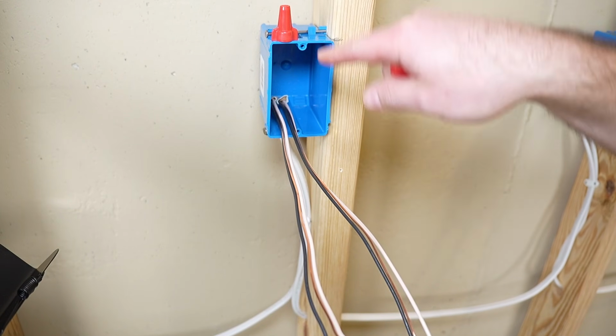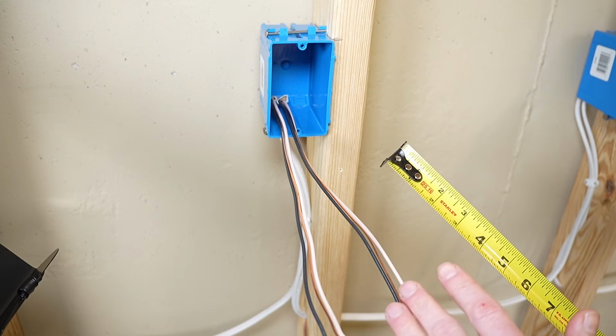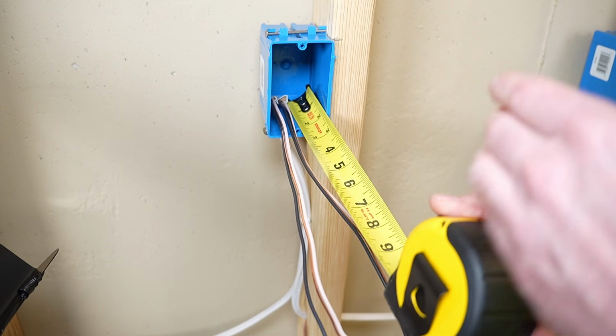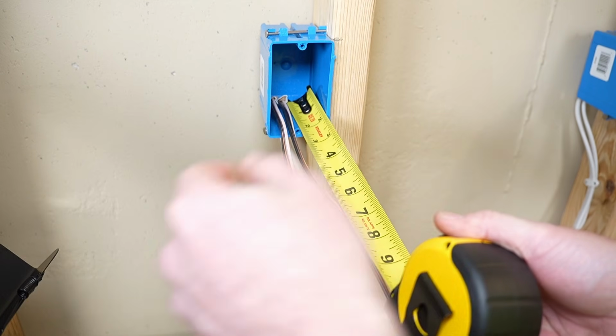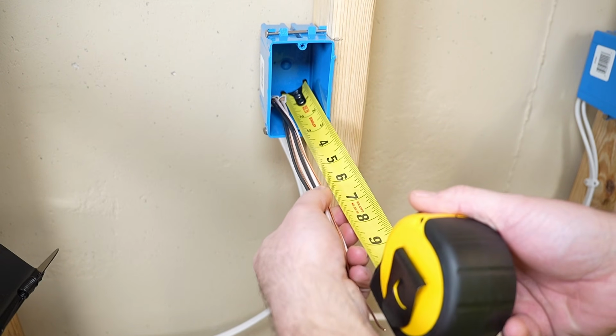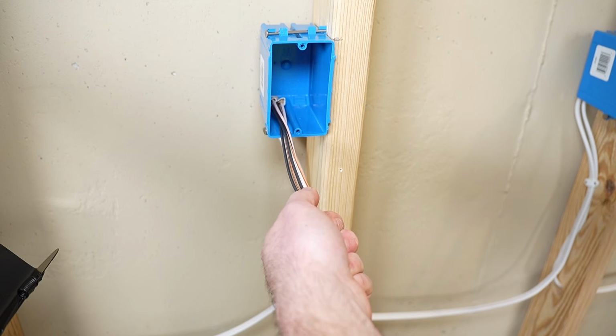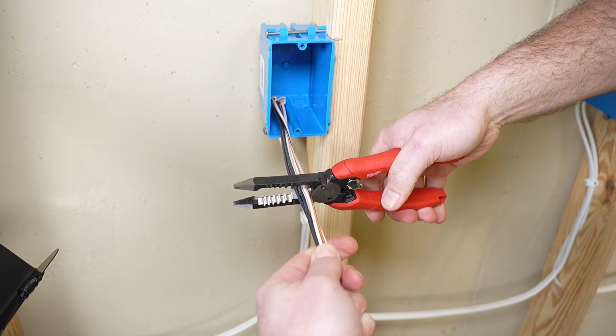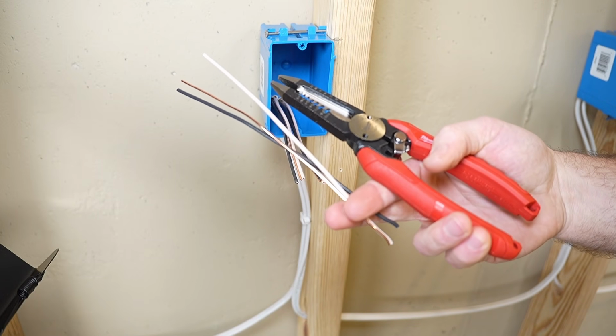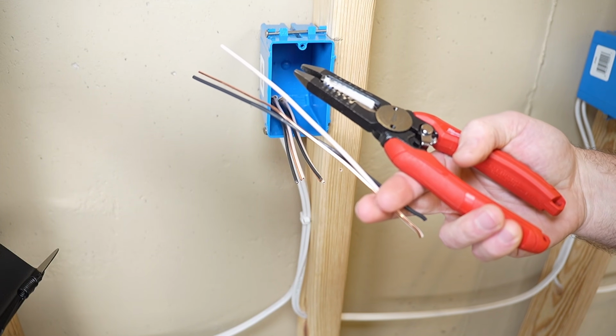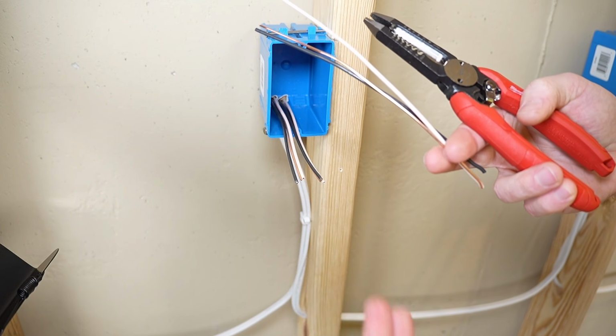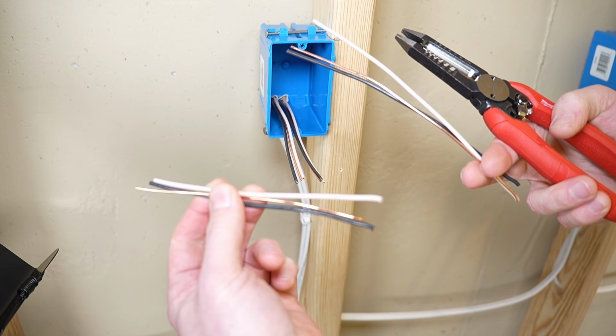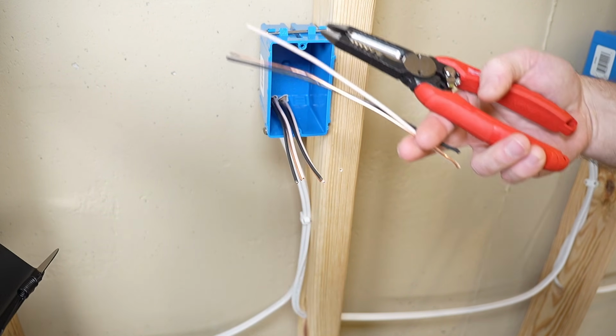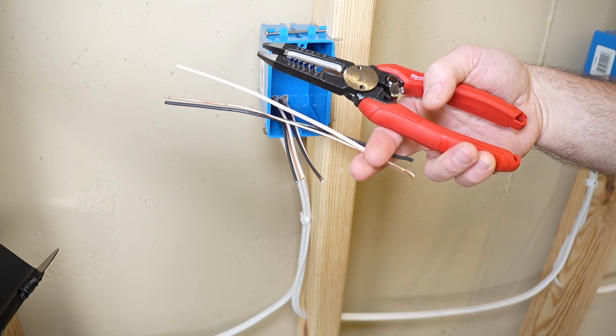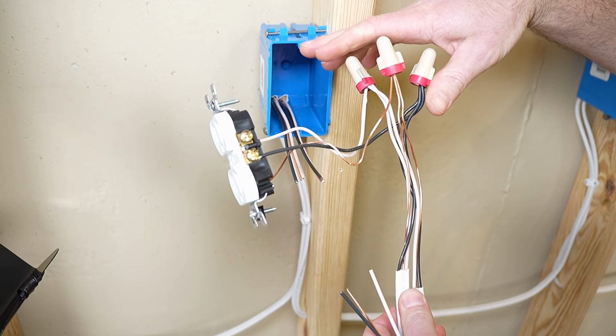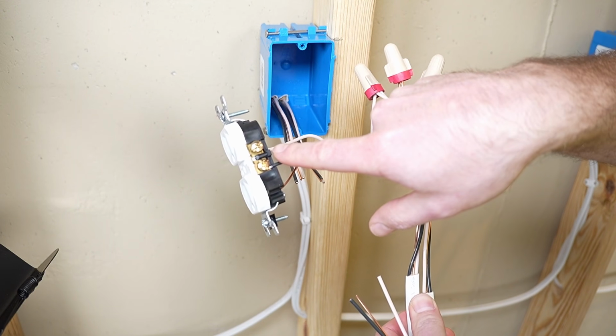So at this first box, we are going to be splicing using wire nuts. Now the code says we have to have at least 6 inches of free conductor from where the cable enters the box. So we're going to want to cut these wires approximately right here, 6 inches from where it enters the box. I'm just going to cut all of them at the same time. I'm going to use some of this scrap as our pigtails. So really, we're not wasting anything by having extra wire there. Sure, this little bit of shorter ones right here, this is scrap, but this we're actually going to use as our pigtails because we need some wires to go from our wire nut splices to the receptacle itself.